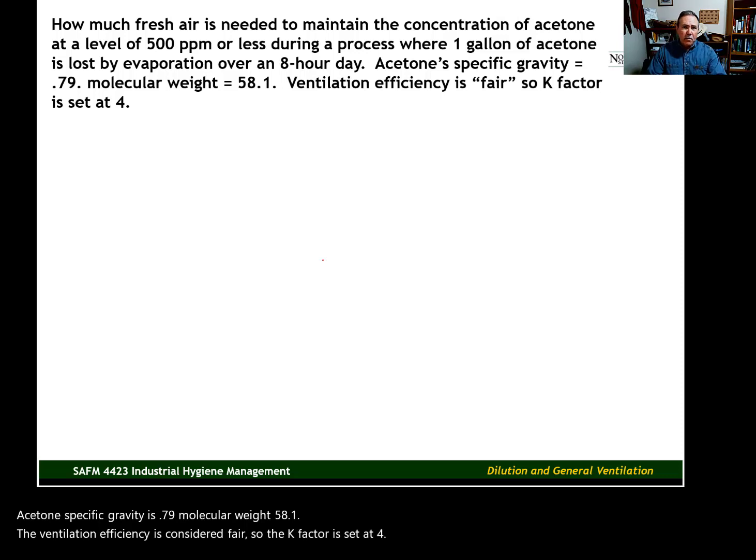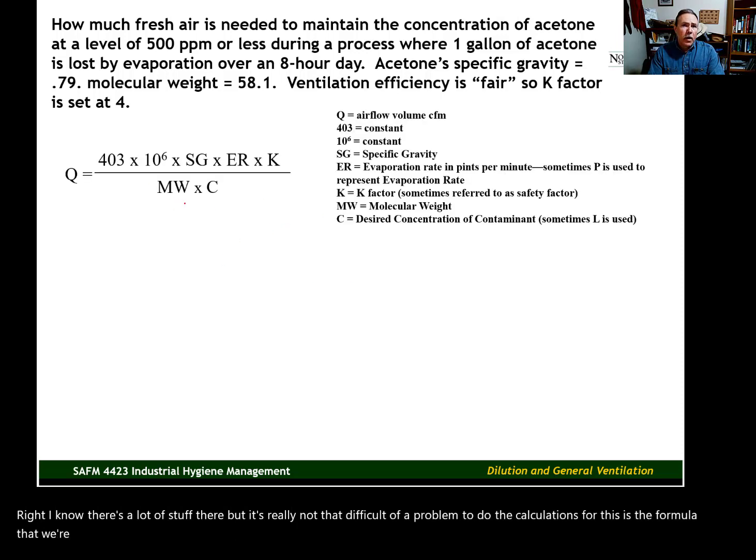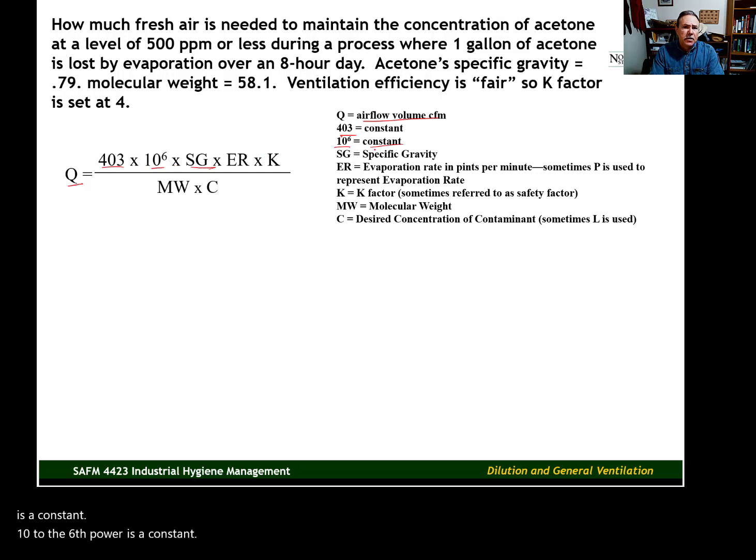I know there's a lot of stuff there, but it's really not that difficult of a problem to do the calculations for. This is the formula that we're going to use. Let me go ahead and work through all the different components of the formula. Q is the airflow rate or volume that we're calculating, and it's the volume in cubic feet per minute. 403 is a constant. 10 to the sixth power is a constant. SG is specific gravity. ER is the evaporation rate in pints per minute.